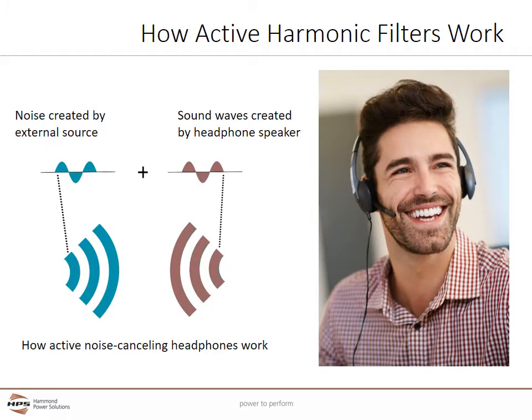A good comparison for active harmonic filters is noise-canceling headphones. To cancel the lower frequency portions of audible noise, noise-canceling headphones use active noise control — incorporating a microphone that measures ambient sound, and a small speaker in each ear that generates an audible waveform that is the exact negative of the ambient sound. The headphone's microphone acts the same way the active filter's current transformers work. Rather than using speakers to generate an equal but opposite noise, active harmonic filters generate currents equal but opposite to the harmonic currents and inject those into the system.